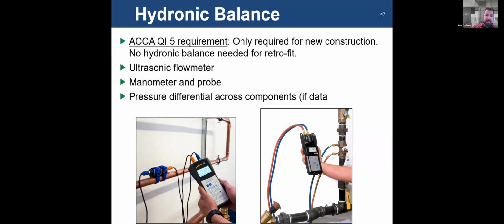So, something to note. It can be done directly with a flow meter shown in the bottom left, or you can use a manometer and probes, basically measuring pressure. The simple way is to use this picture on the right, a differential pressure meter for water. It measures differential pressure for you across either a component, or in this particular case, a balancing valve. So you'll measure differential pressure across that balancing valve. Balancing valve manufacturers have charts that correlate the pressure that you measure with the valve setting and tell you what the actual flow is based on that differential pressure measurement. And then that can be adjusted. So you can allow more flow or less flow depending on what the requirement is.